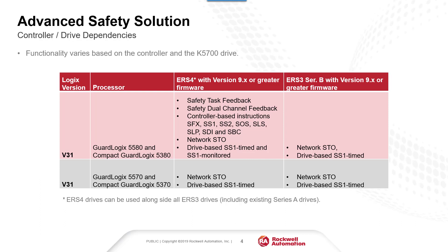When using the Kinetix 5700 ERS-3 Series B drive with an L8 GuardLogix controller, network STO and drive-based SS1 timed are available. If using an L7 GuardLogix controller, the feature sets are the same for both Kinetix 5700 models: network STO and drive-based SS1 timed. Note that ERS-4 drives can be used alongside all ERS-3 drives, including the existing Series A drives.